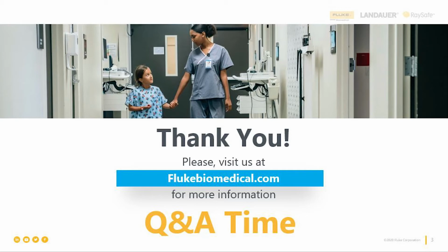Having the proper height level already figured out, having, as Mick said, the ability to collect all of the parameters in a data log on the same time base really helps. It's not just a test here or a test there. It's across the time that we're trying to assess the performance of this incubator. The rise time till we get stable temperature, the stable temperature control, that's called STC in the standard, so that we're sure that not only does it reach the right temperature, doesn't overshoot too much, but that it stays relatively stable between the band of control of the temperature.